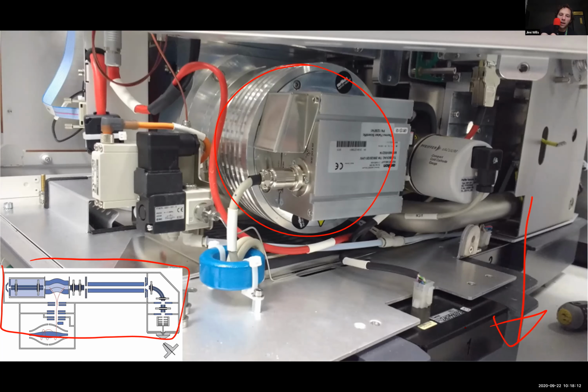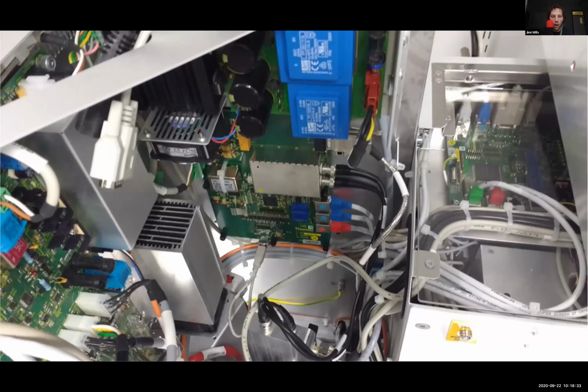But this thing then takes individual molecules and pings them out of the internal space of the mass spec, so that there are no molecules in there that can interfere with your ions that you're trying to control. And at the top, there are lots of circuit boards. These are control boards or RF readout boards that are sending or receiving information to the various devices.